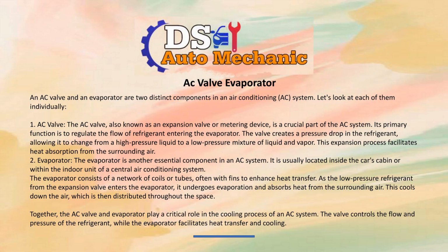1. AC valve. The AC valve, also known as an expansion valve or metering device, is a crucial part of the AC system. Its primary function is to regulate the flow of refrigerant entering the evaporator. The valve creates a pressure drop in the refrigerant, allowing it to change from a high-pressure liquid to a low-pressure mixture of liquid and vapor. This expansion process facilitates heat absorption from the surrounding air.